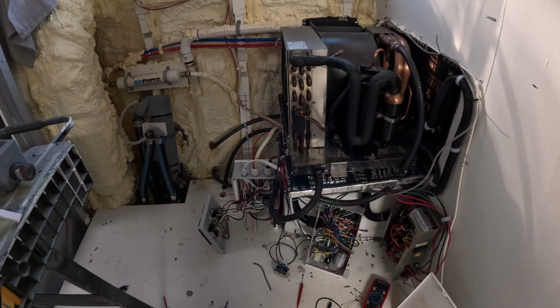Later, I was taking pictures of the other unit, looking for a serial number and information like that, so when I contact them on Monday, I can say here's what I'm doing, here's what I'm seeing. The label on the unit has a check mark for whether it's 220 or 115. This was supposed to be a 115 unit, was my understanding, but what's checked is 220. If this is really 220, that would certainly explain why nothing does anything when you turn power on.